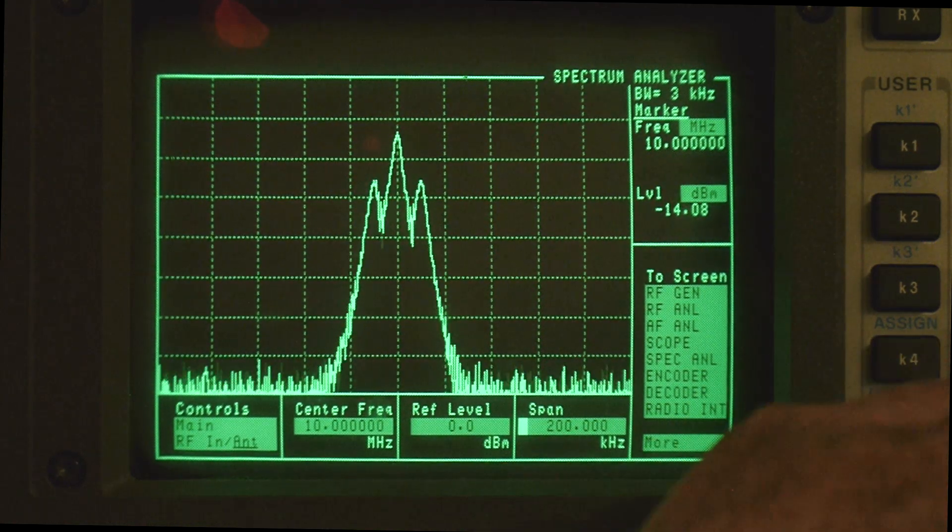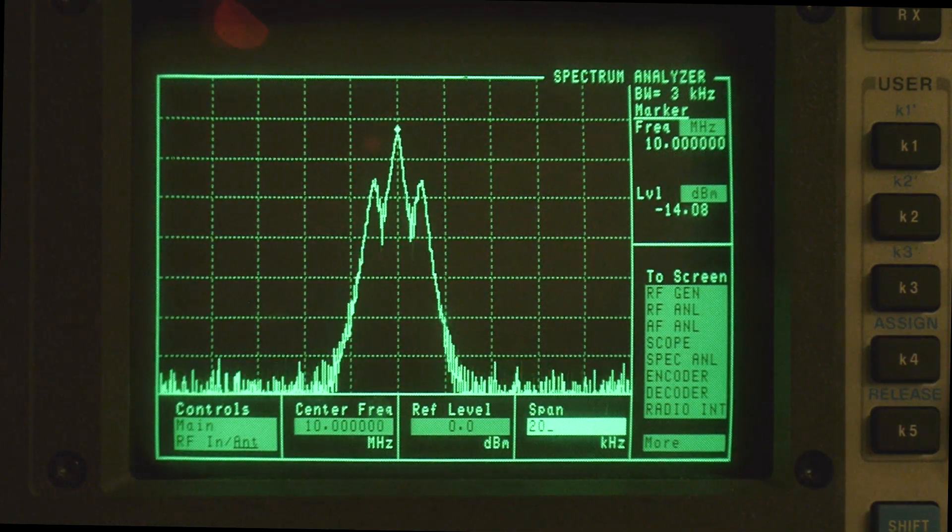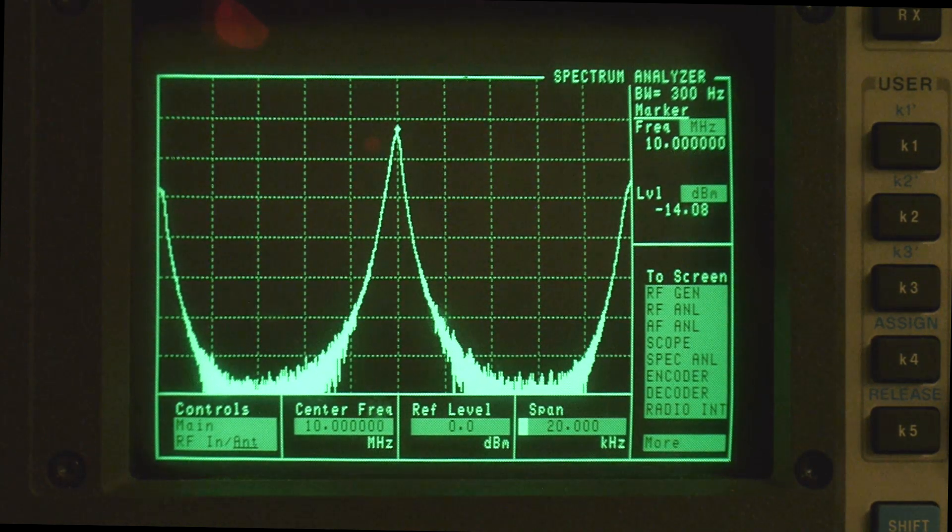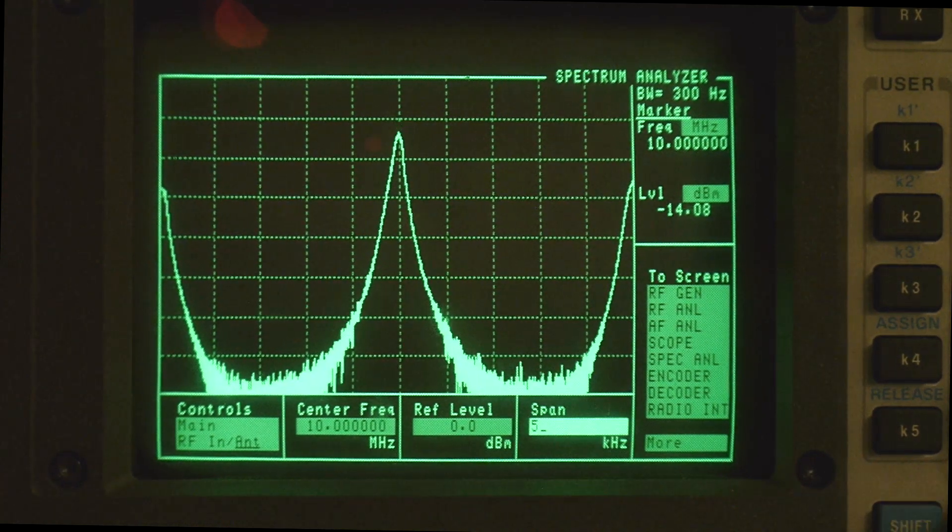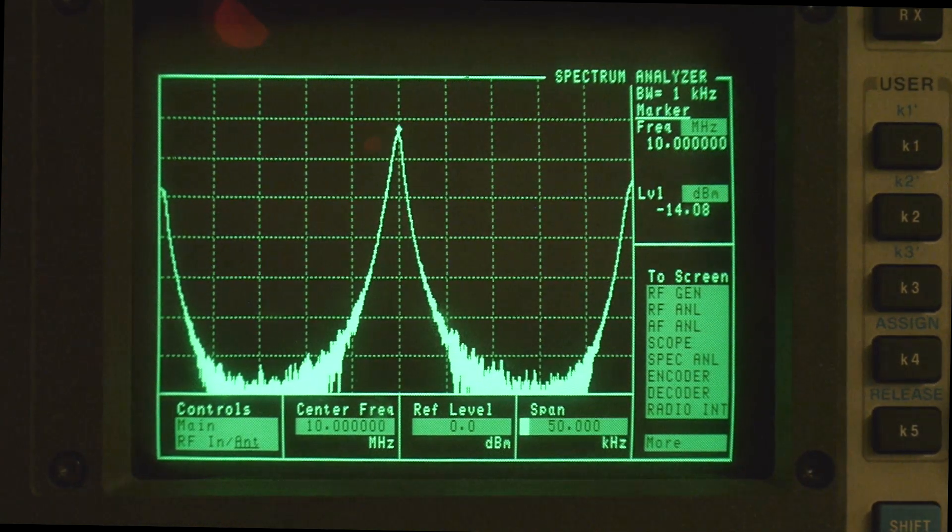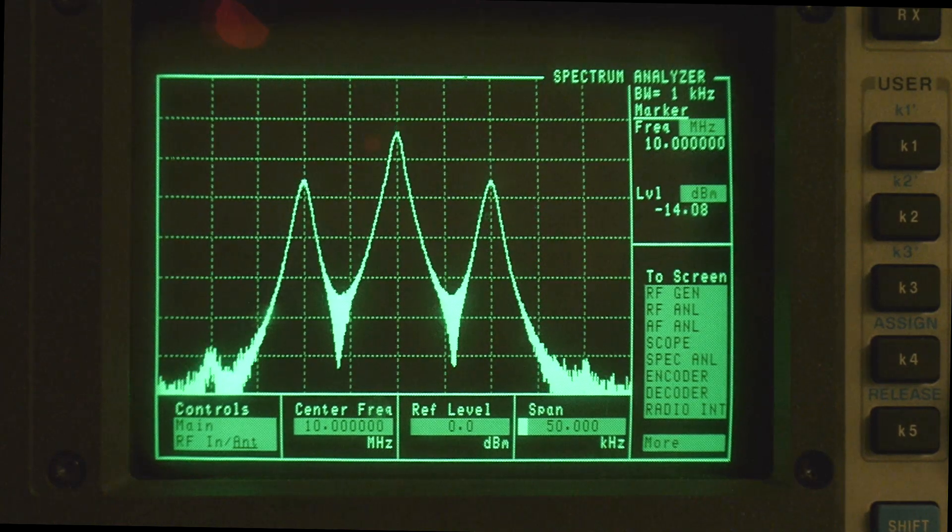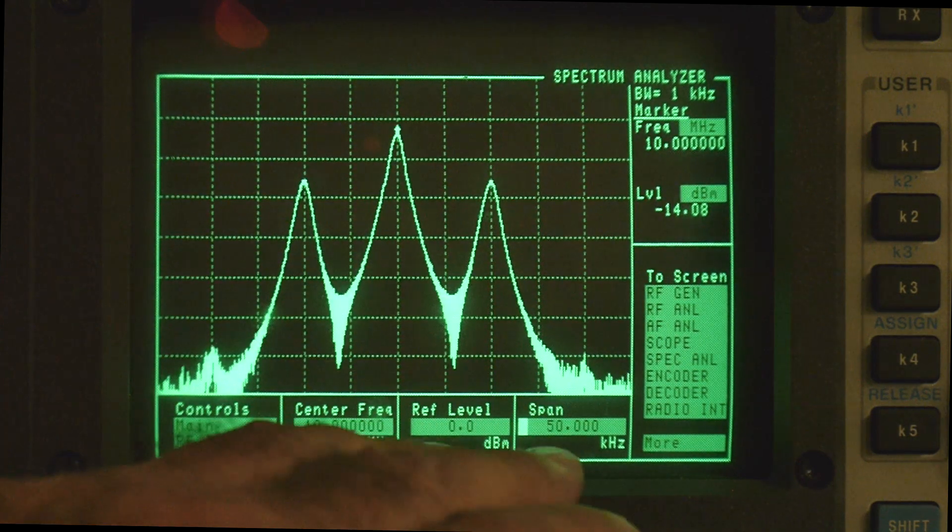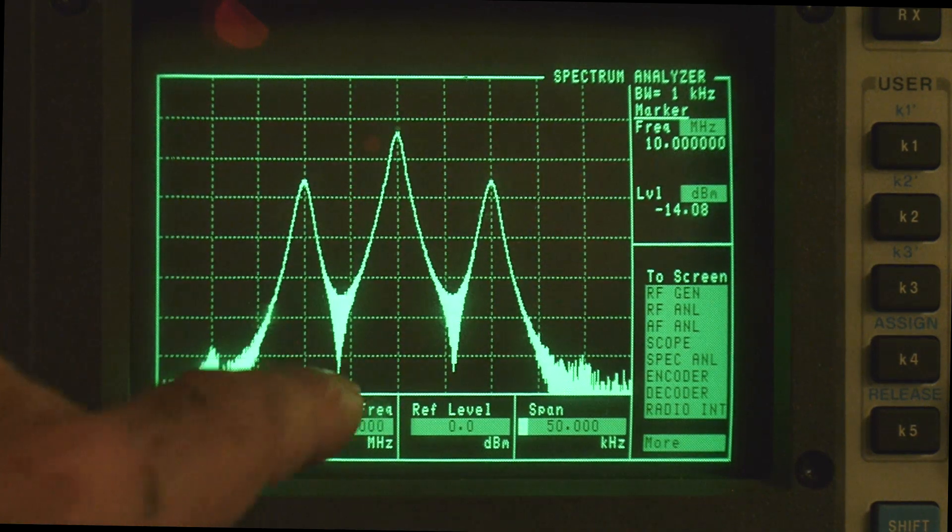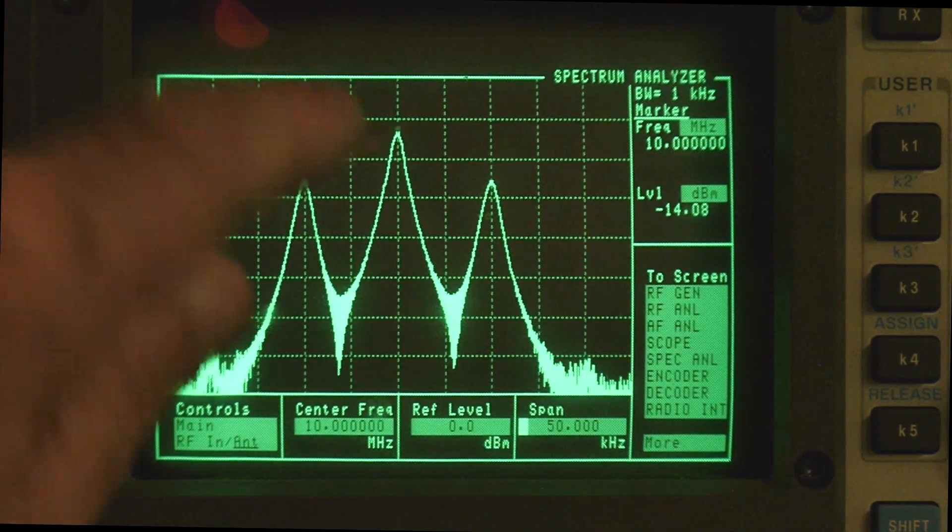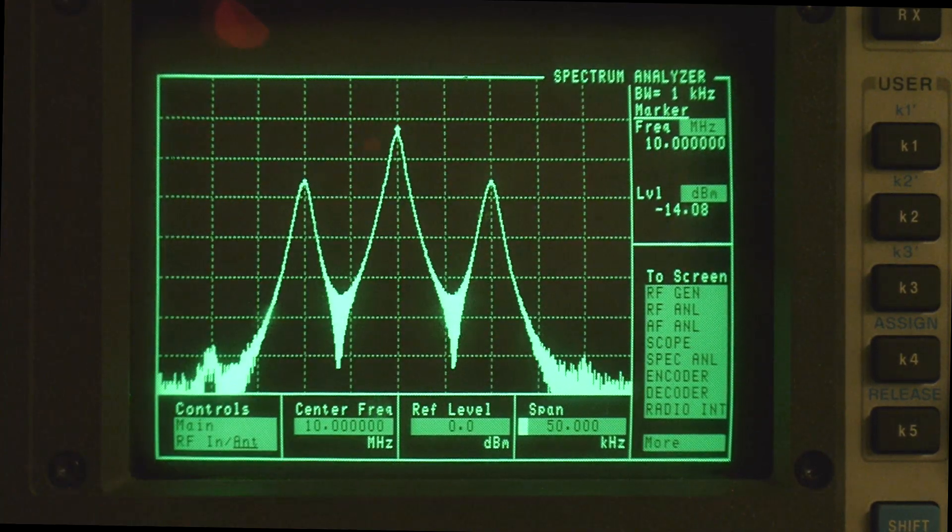In fact, we can zoom in on this. So if I change my span from 200 kilohertz to 20 kilohertz, I've gone too far. Let's see here. I'll change this to 50 kilohertz. There we go. So these are the 10 kilohertz carriers, and you can see that we're seeing those really, really well. It's very easy for us to determine those.